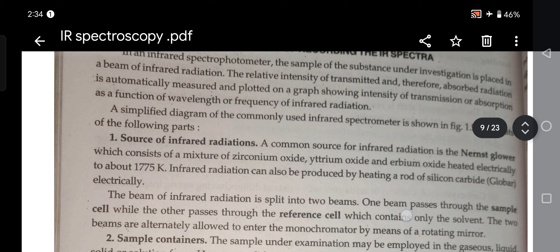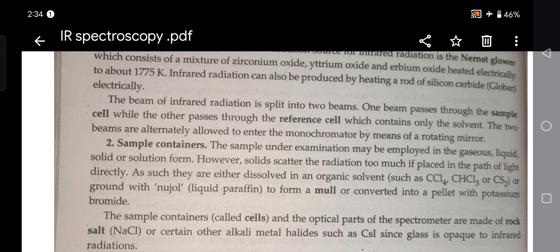A simplified diagram of a commonly used infrared spectrometer is shown in figure 1.5. It consists of the following parts. First, source, the source of infrared radiation. A common source of infrared radiation is the Nernst Glower, which consists of a mixture of zirconium oxide, yttrium oxide, and erbium oxide heated electrically to about 1775 Kelvin. Infrared radiation can also be produced by heating a rod of silicon carbide.